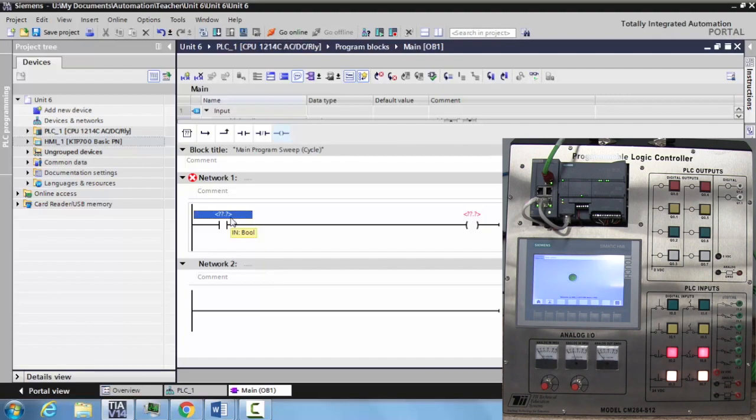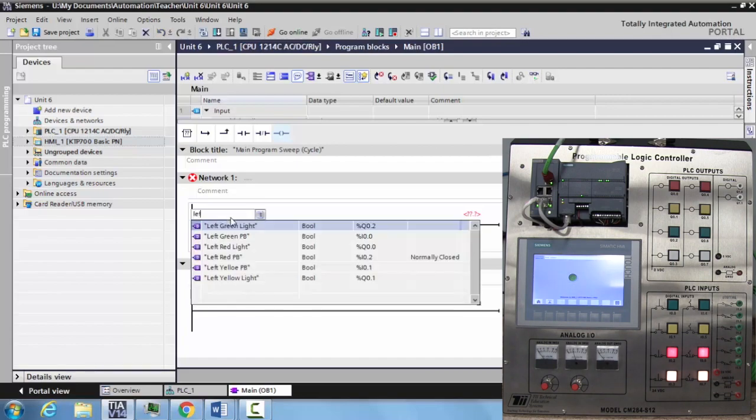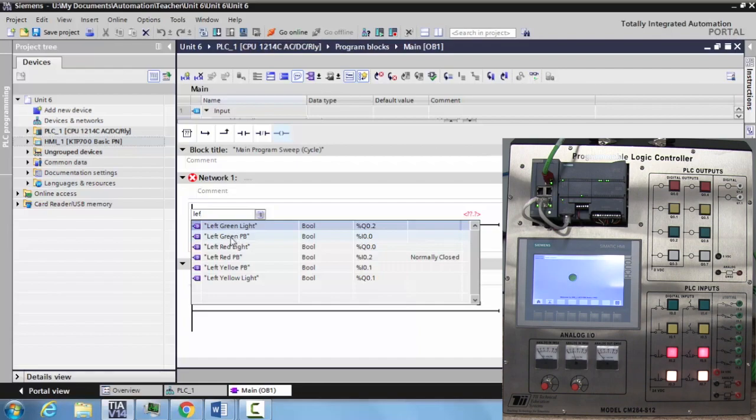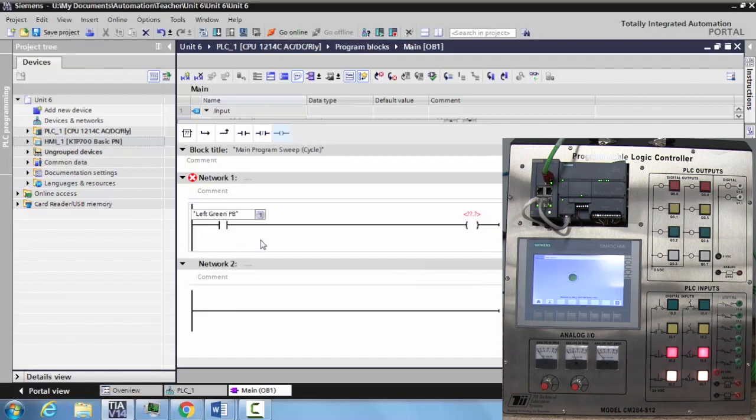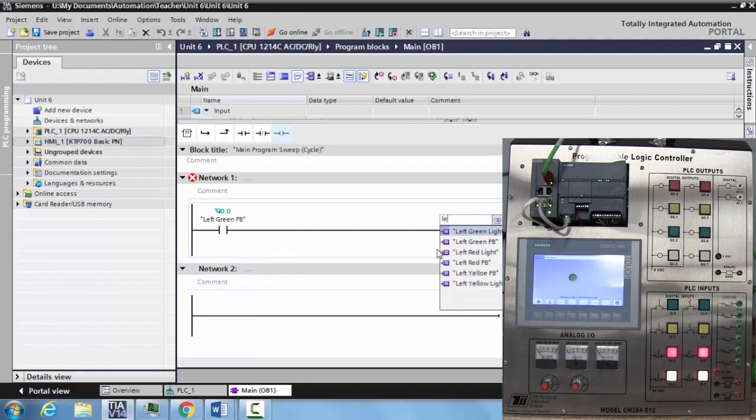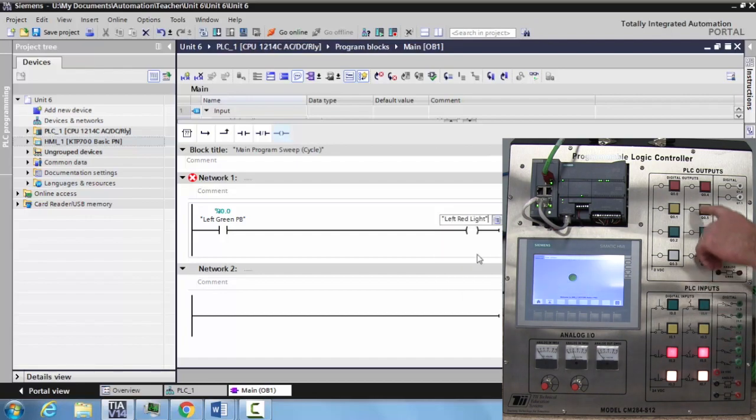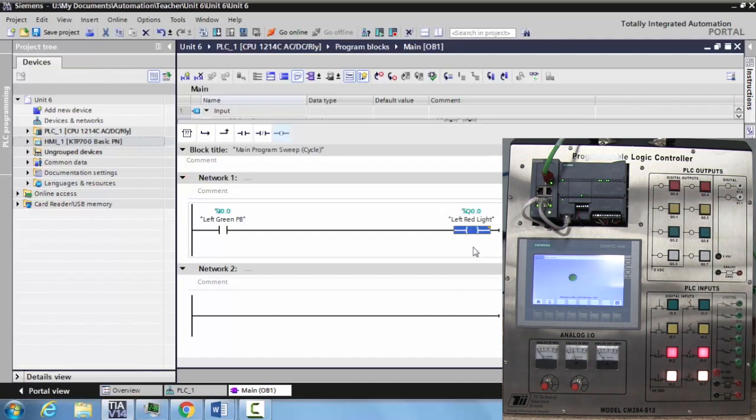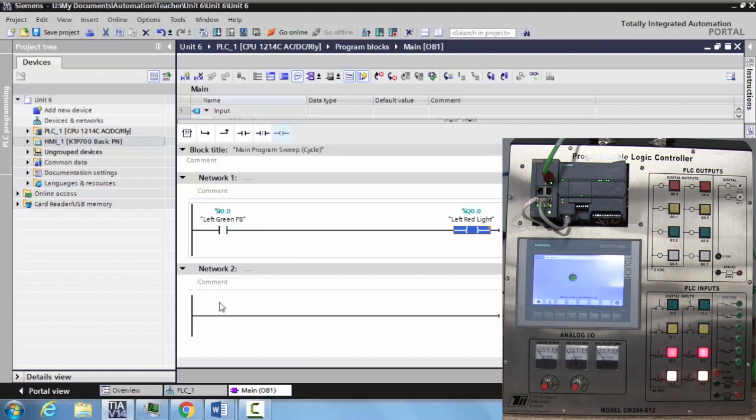All I have to do is come over here and start typing left, and you can see the tags pop up. Now if your tags are similar, you've got to pay extra special attention to make sure you don't click on the wrong one. So we're going to do the left green push button, select this, hit enter. And then for our output, we'll just put left red light right here. As you can see, they are already tagged to the inputs and outputs that we associated with them when we were in the PLC page.